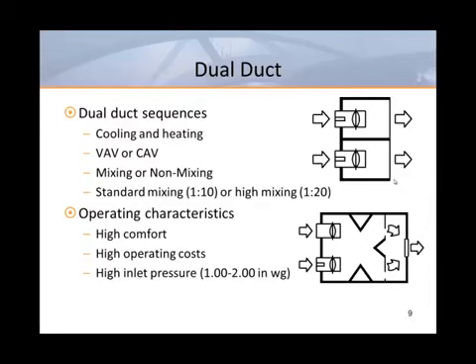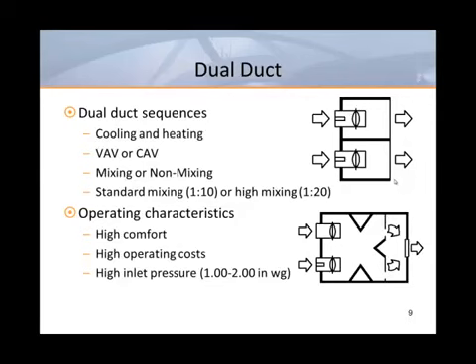Dual duct boxes without mixing chambers should only be used in non-mixing applications — these units provide cooling or heating, but not at the same time. A mixing chamber is absolutely necessary for blending hot and cold air streams together. The standard mixing ratio for dual duct boxes is a 1 in 10 ratio, meaning that for every 10 degrees of difference in the hot and cold supply temperatures, there will be no more than one degree of temperature variation at the discharge duct. High mixing boxes provide 1 in 20 mixing. With the high costs of operating dual duct systems, the market is somewhat limited, but there is renewed interest in dual duct boxes for mixing conditioned air with air from dedicated outdoor air systems. An optional water coil at the discharge could be used for heating without the need to actually reheat.